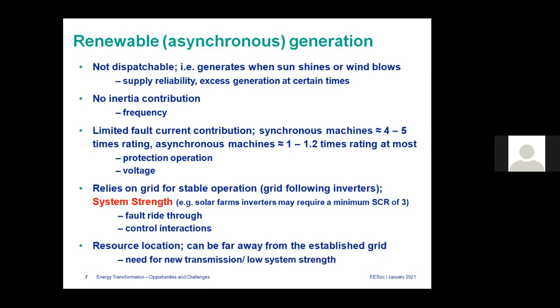or system strength. And another issue with these renewables is the location, because most of the established grids are near the synchronous generators. Even in Sri Lanka, I think there are more transmission lines coming from the hydropower stations. There are lots of transmission lines to the load centers near Western Province from the hydropower stations. But if you go to Hambantota or even up north, the number of lines you see is much less. So there will be a cost for new transmission.